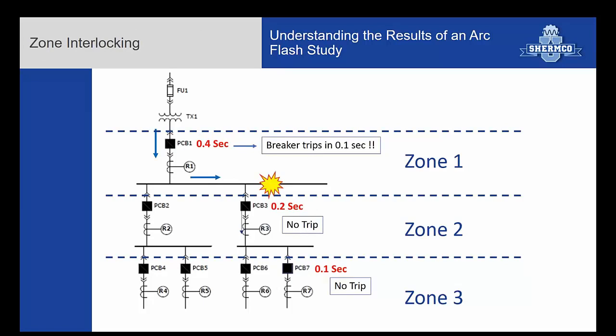Okay, we're going to talk about a few other items that people use to reduce arc flash current. Zone interlocking, typically used in low voltage gear, is very common. With zone interlocking, the way it works is if you have a tree of breakers like this, a main feeding 2 feeders, if the main sees the fault, then it's expecting a signal from one of these other 2 breakers saying they see the fault as well. If it doesn't get a signal from either other breaker, then it knows the fault has to be in between the 2 sets of breakers.